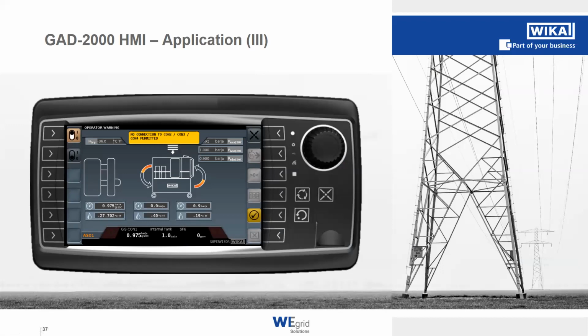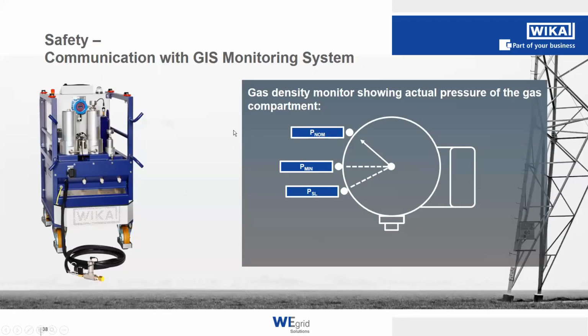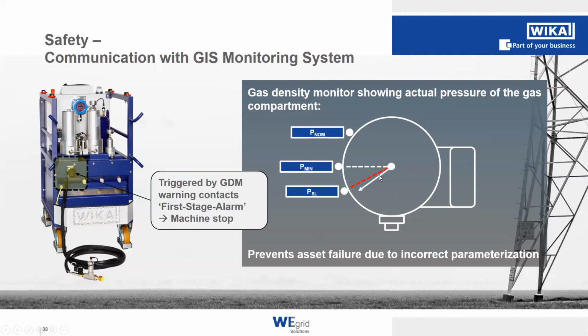And when the set values parameters are fine, you start the application process by just cycling the recovered gas in our GAD unit, always having the most important parameters on the display. Like we can see the humidity level within the gas from the two GDHT sensors I just mentioned, and we also have the pressure inside the gas compartment and the humidity value within the compartment. So again, speaking about the upper and lower limit, if we reach the lower end of the pressure limits, we will trigger a first stage alarm to the machine and automatically completely shut off our unit.